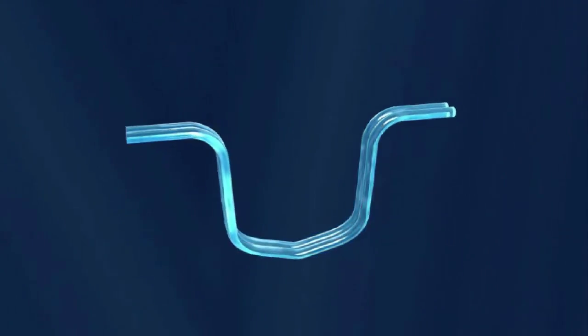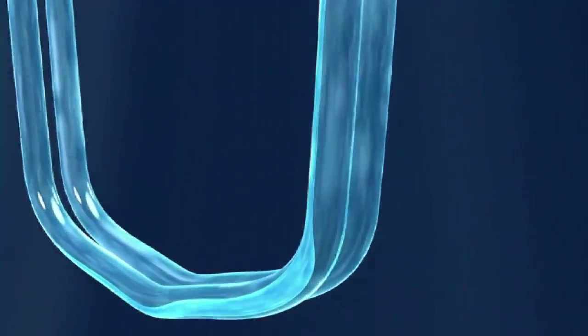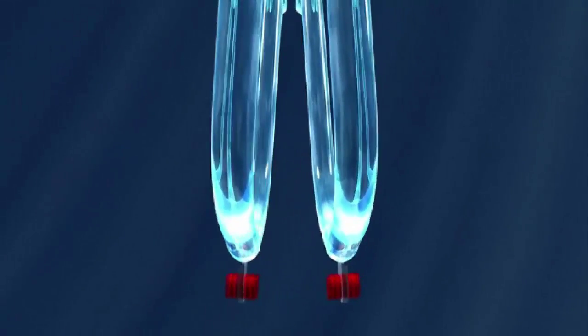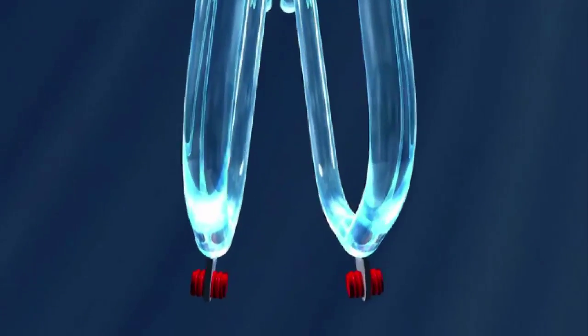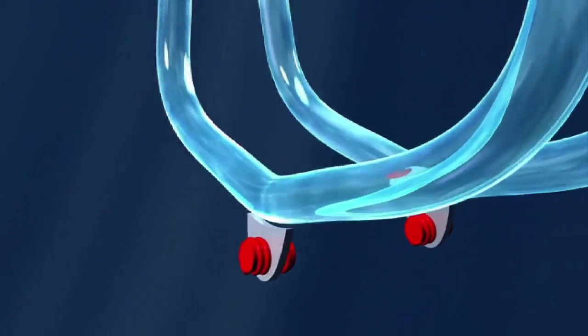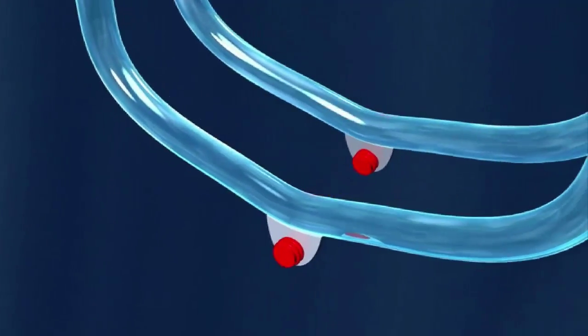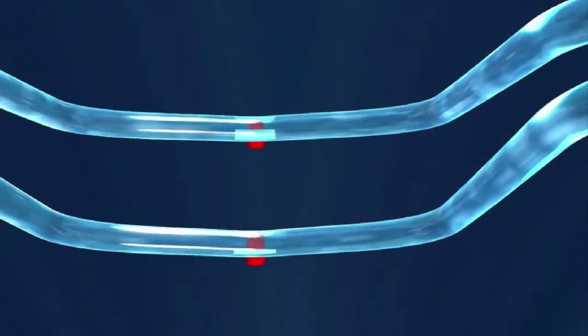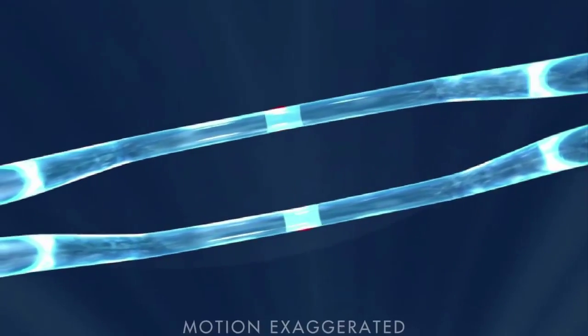For practical exploitation of this principle, it is sufficient for the two measuring tubes to perform oscillations on a small section of a circular path. This is achieved by exciting the measuring tubes with an electromagnetic exciter in its first resonance frequency.